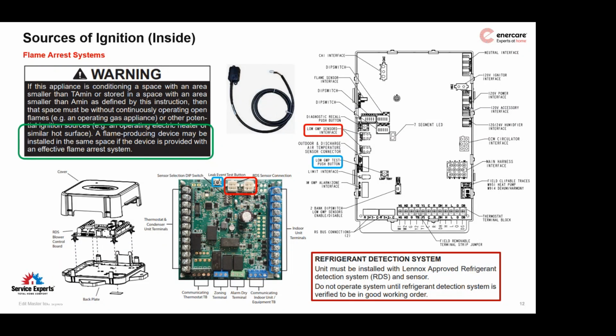But these need to be verified that they're operational, and your final technician install notes or commissioning notes have to say specifically that these systems were tested and proven functional, so that they know, in the event there's ever a leak, that the systems were tested and proven to operate.